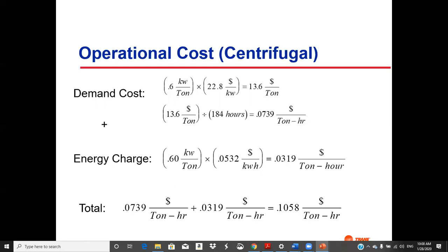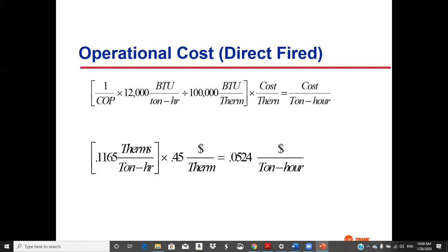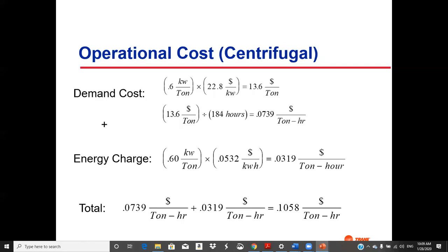The energy charge is straightforward. It's 0.6 kW per ton, and $0.0532 per kWh, so that's 0.03. You add those two together and you get about $0.1058 per ton hour, including demand smeared out over the operating period where we could affect the savings and the energy. So now we're comparing 0.0524 to 0.1058, and we got some savings, about 50% for doing this.